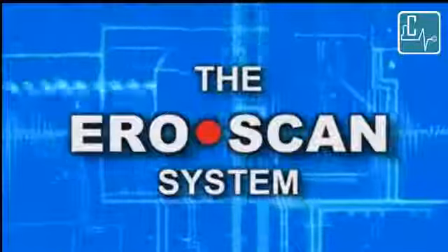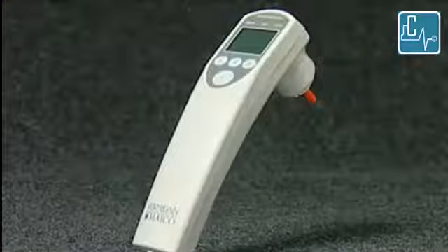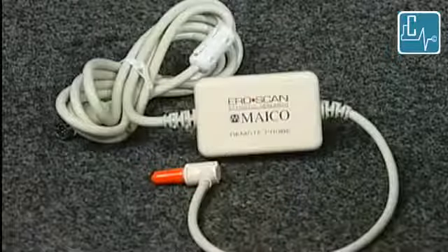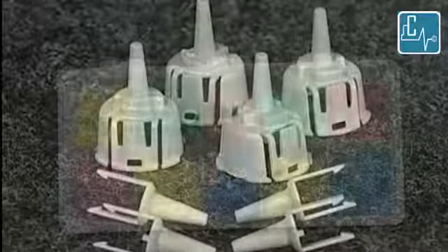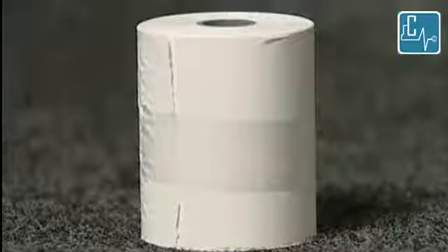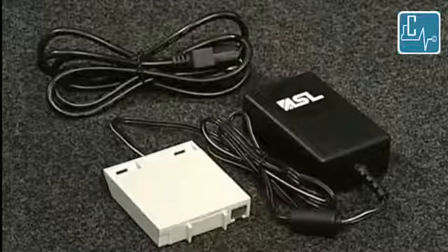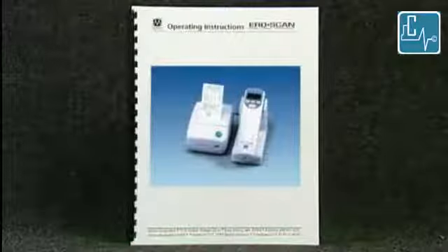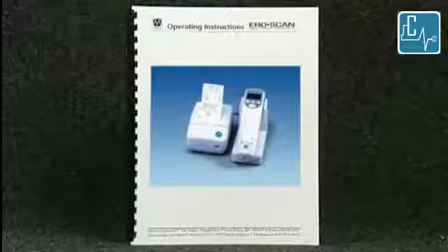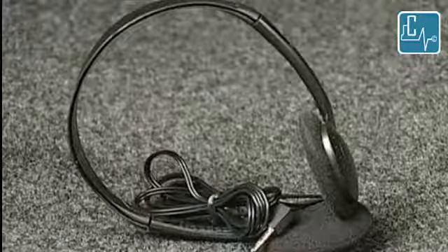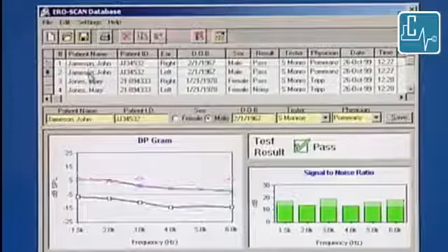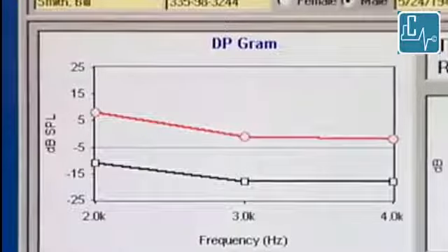The ERO.SCAN system is shipped with the following items: the ERO.SCAN unit, cradle, external probe, probe tips, ear tips in 12 sizes, printer, printer cable, thermal printer paper, power supply, batteries, and manual. Your system may also include one or more of the following: a carrying case, a rechargeable battery, and operator headphones. Also available is the ERO.SCAN database software. This software allows the user to archive, display, graph, and print test results for each patient.